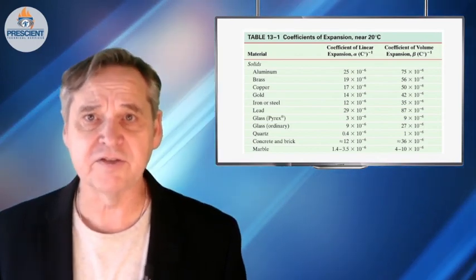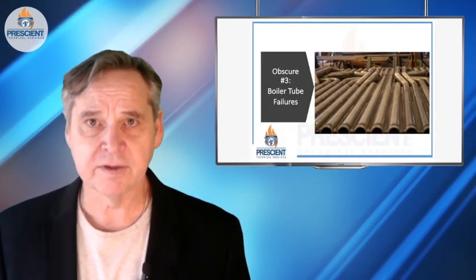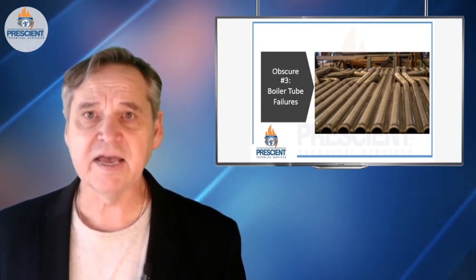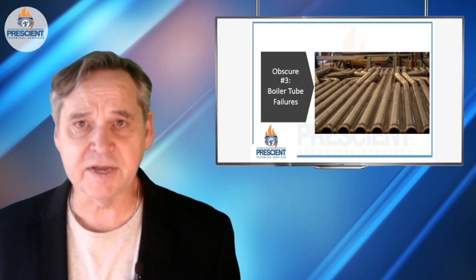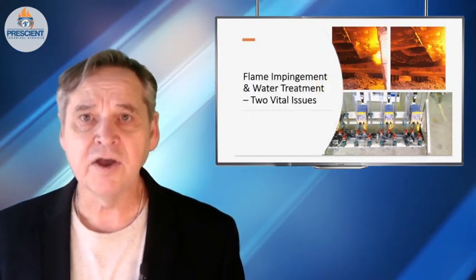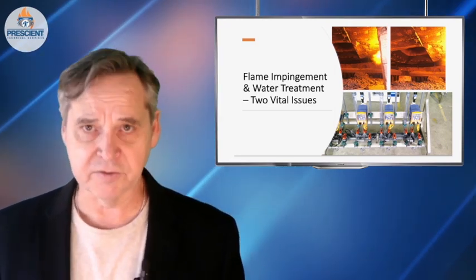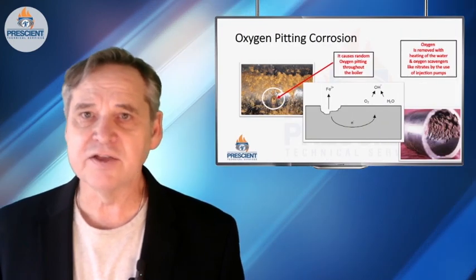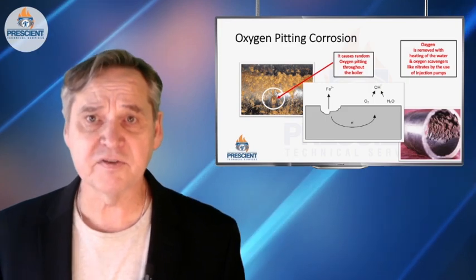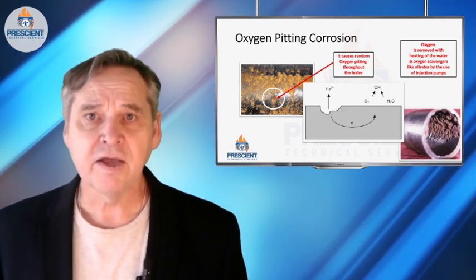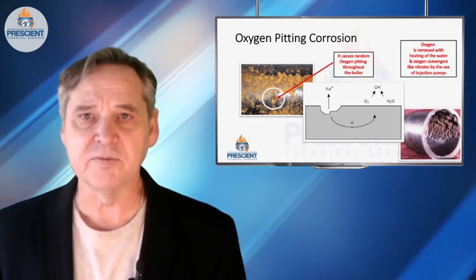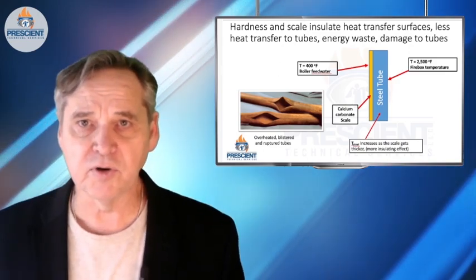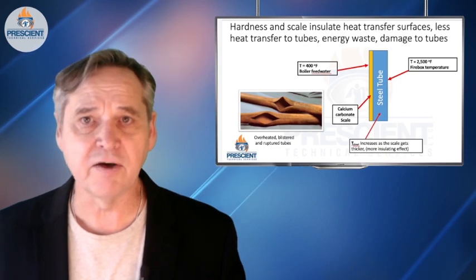Obscure issue number three is boiler or furnace tube and mechanical integrity issues — and I'll focus on the case of boilers, though it's the same issue for a refinery heater, for example. The issue is that if your water treatment is not correct, or you've got flame impingement on tubes, you dramatically reduce the useful life of this equipment and it sneaks up on you. You can't readily observe the internal condition of tubes. There are some failure mechanisms, especially in the water treatment world, which are catastrophic. If you start to have oxygen pitting, it can happen randomly throughout a number of different tubes. If you bleed through hardness and start depositing calcium and magnesium within boiler system tubes, you'll start to overheat them, blister them, and they'll fail.